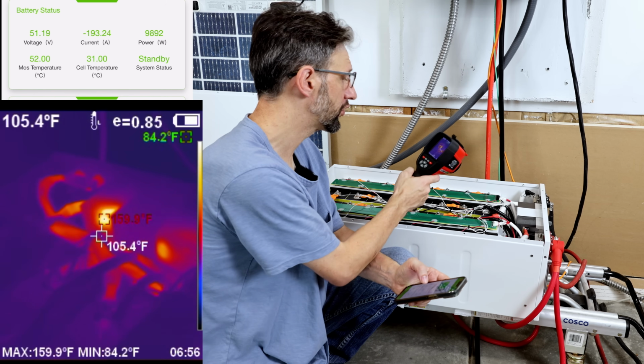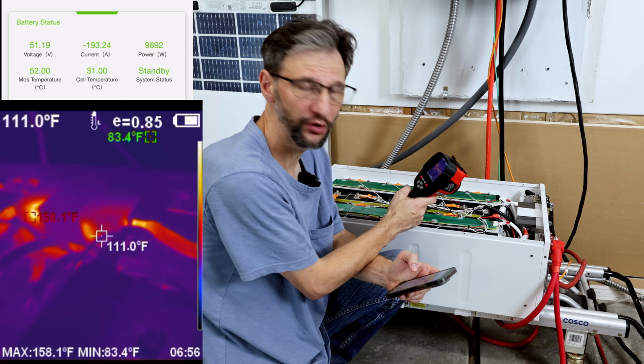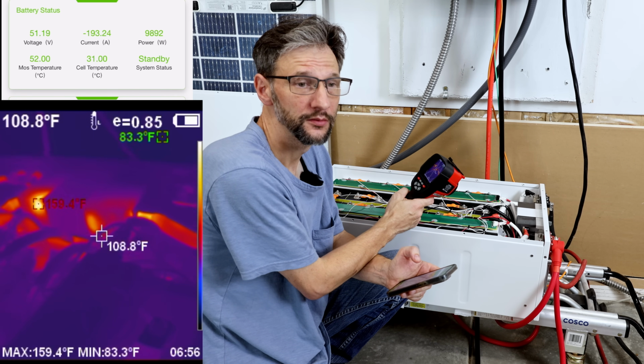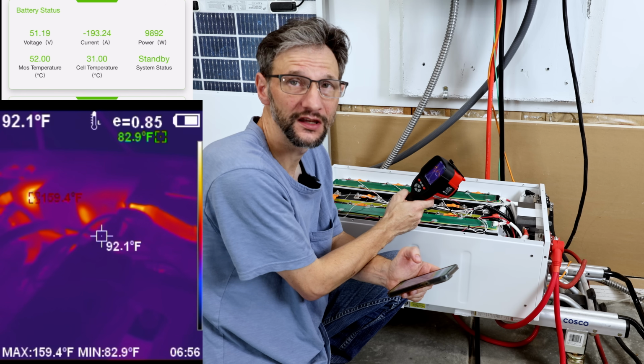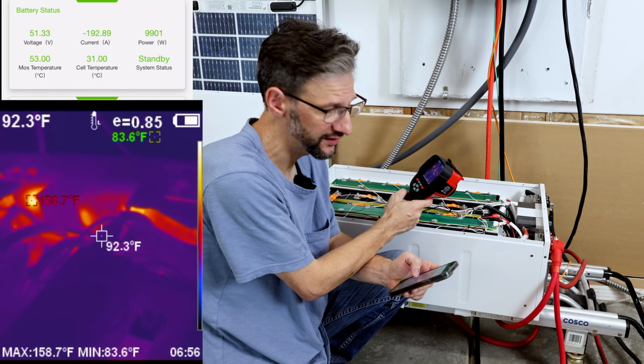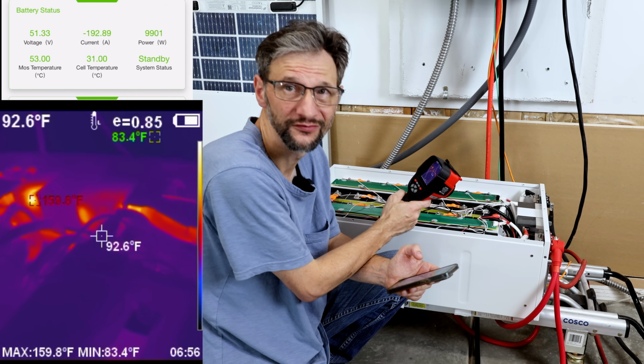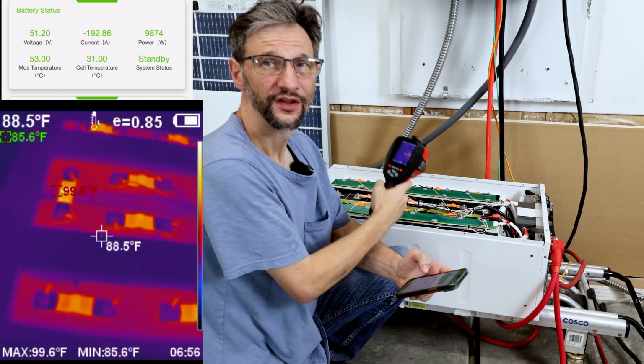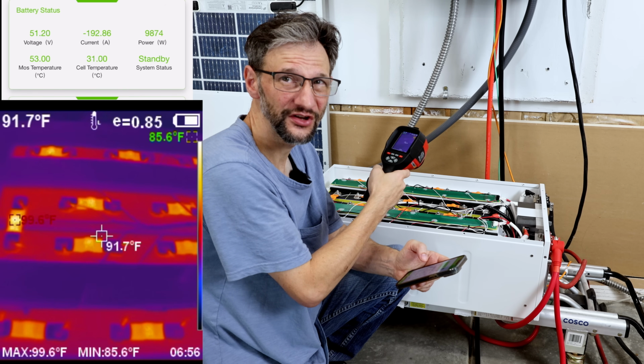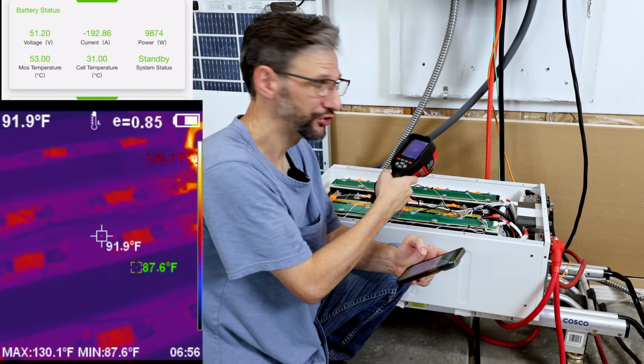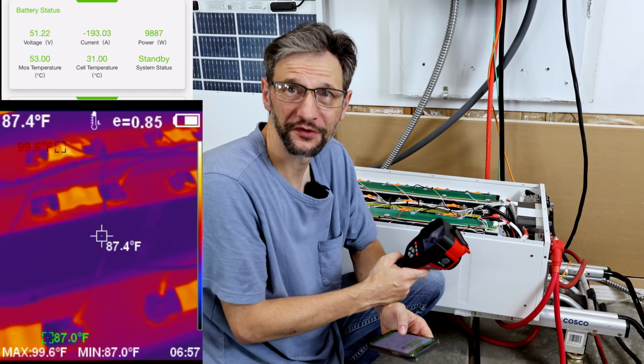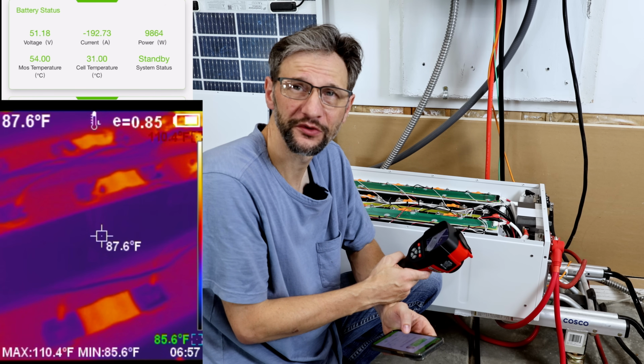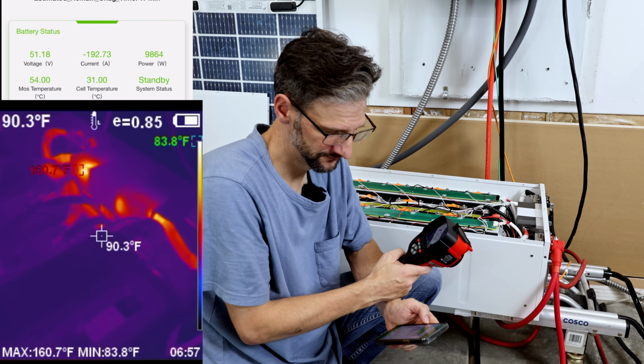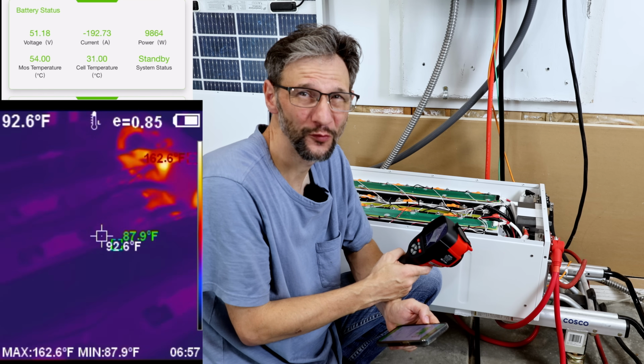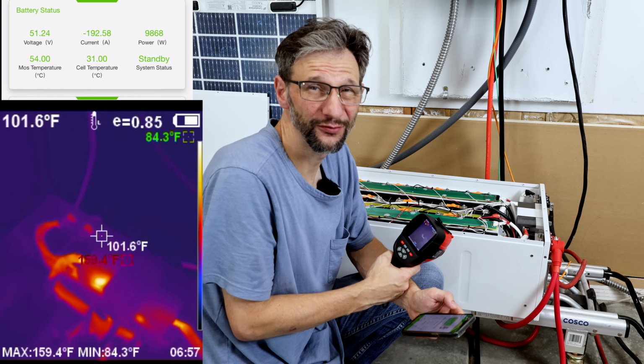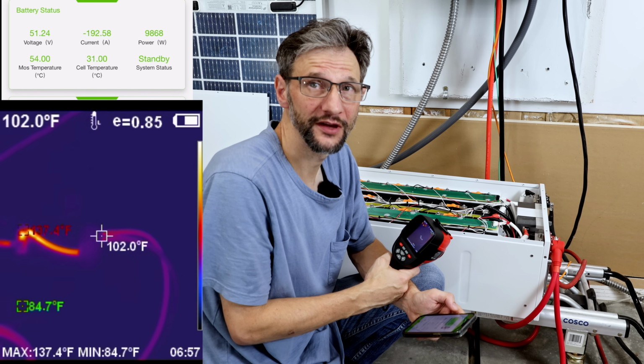The breaker's fairly warm, and I mean, you're going to have that with a breaker. They're designed to be tripped by heat, so it has to get warmer as you get closer to its limit, and it's a 200 amp breaker, so we're running right at its limit. The rest of the battery and all of its connections are super cool, no problem. I'm pretty happy with that performance. Everything's within a tolerable limit, right at its 10,000 watt max. I'm going to let this run for a while at its max and see if we have any issues.